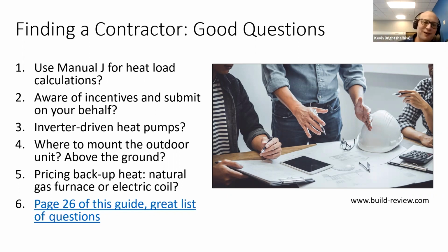But inverter or variable speed heat pumps, basically they modulate how much energy they're using based on the outside air temperature that they're operating within. So if it's 40 degrees and your thermostat calls for heating, you don't need your heat pump to run 100% to provide heat to your house in that condition. If it's 5 degrees or 0 degrees out, your heat pump will probably need to run close to 100% in order to help heat your house in those conditions. But being able to modulate in between that worst case condition and other conditions that your home might experience all helps save energy. So asking for an inverter driven or variable speed is a good idea.